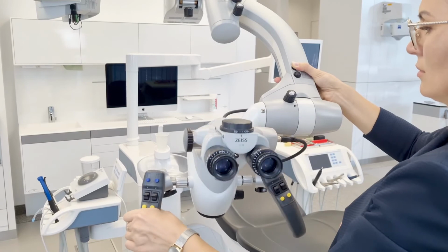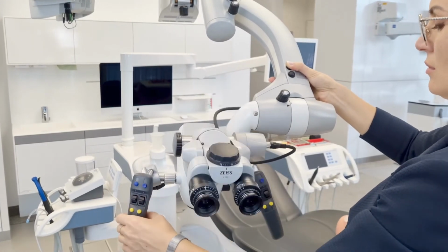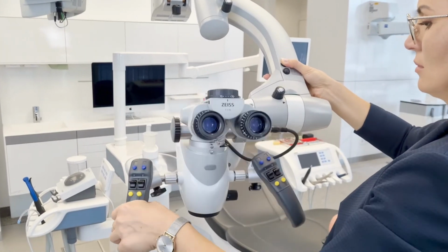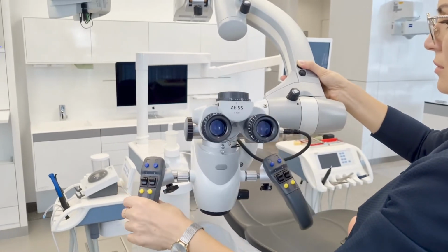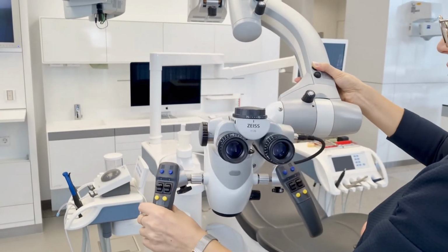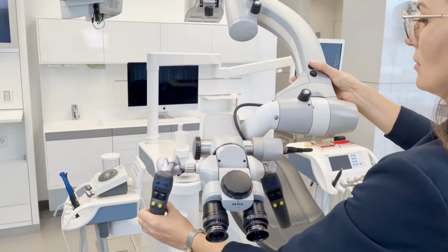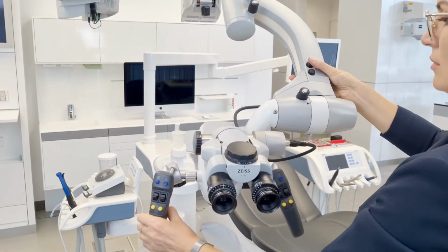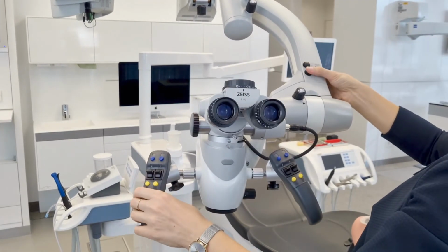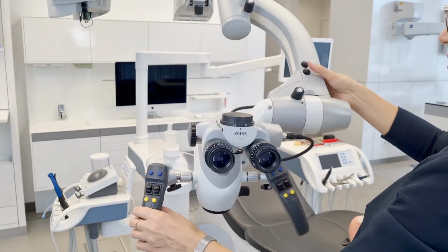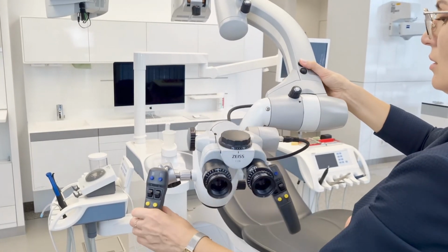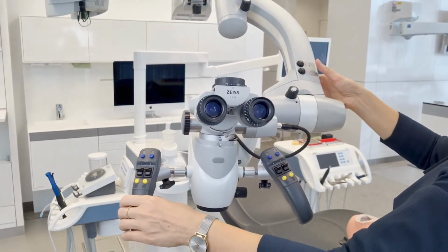To check, slightly lift the surgical microscope body and tilt it into different positions to see whether the surgical microscope body has been correctly balanced. The OPMI head is balanced if it remains stable in each position. If you pressed button 2 too long, you can correct the balance setting by pressing button 1.